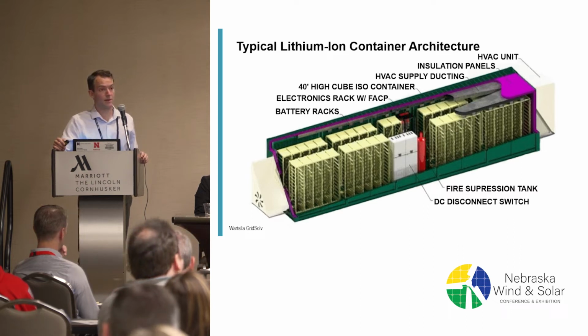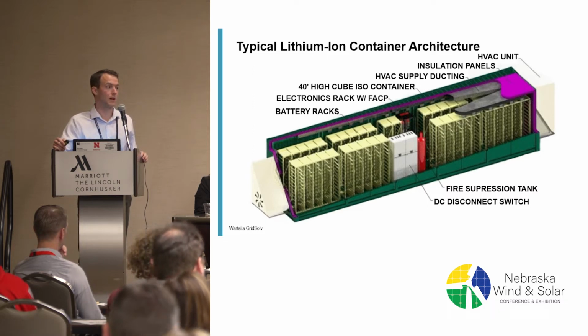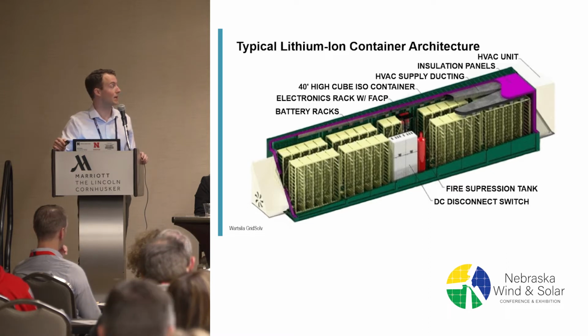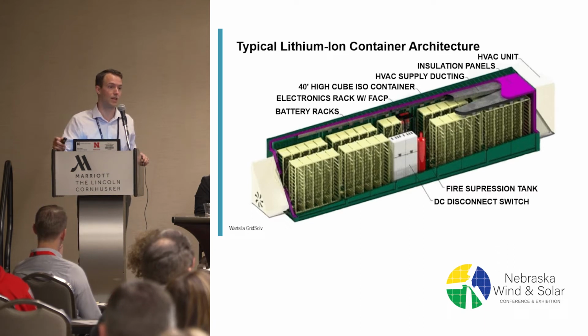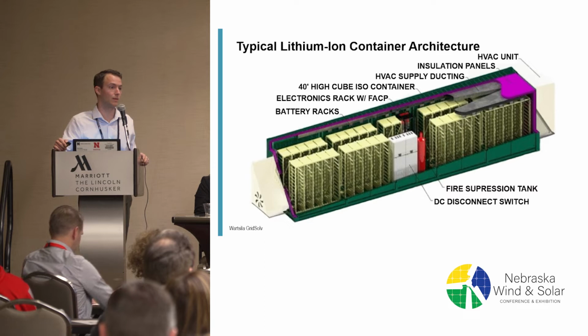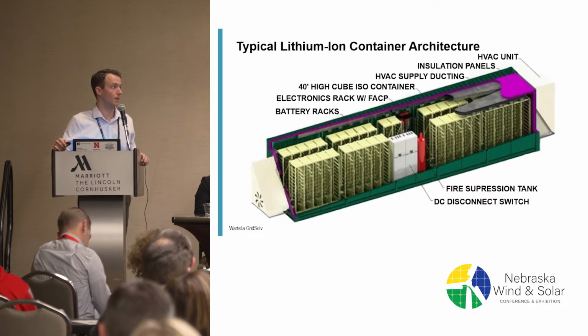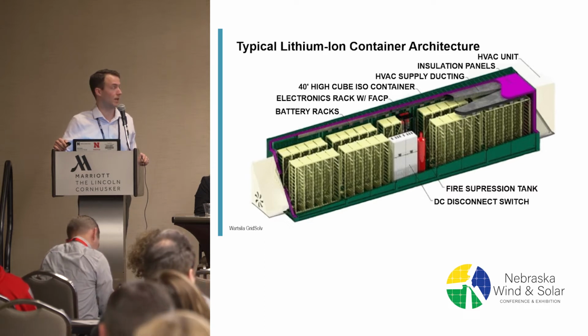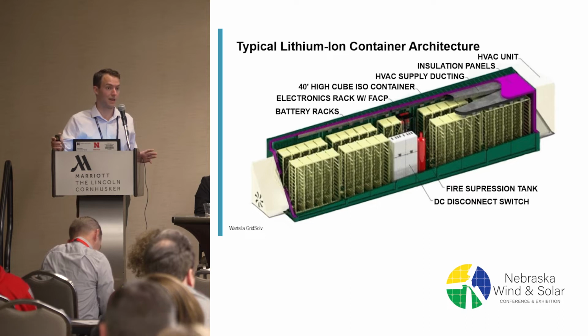Generally, lithium-ion batteries are pretty particular about the temperatures they operate in. Much like us, they prefer room temperature, more or less, and if you can keep them within that tight bandwidth, they last much longer than if they deviate. If you charge and discharge them at high or low temperatures, you get some pretty serious degradation behavior. So in order to maintain that, some very robust HVAC systems are generally required for these containers.